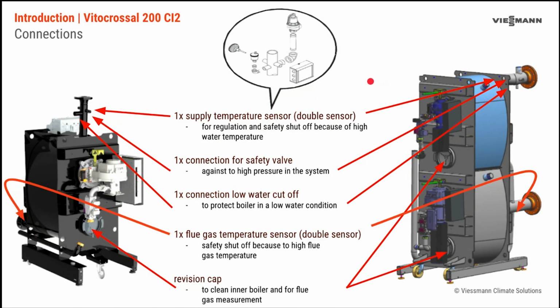This is a double sensor, essentially two thermistors reporting back boiler supply water temperature to the control. We'll also have our safety relief valve connected in the supply sensor and a low water cutoff, which is included in the boiler parts. Flue gas temperature sensor on the rear of the boiler in the flue outlet, and again, a double sensor, so two thermistors, both reporting back to the control.